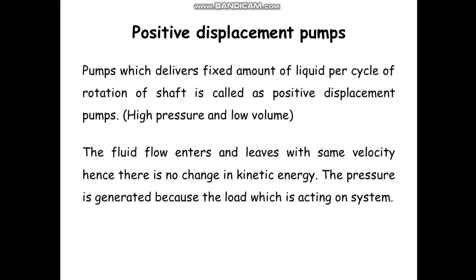So positive displacement pumps, as I already said, deliver a fixed amount of liquid per cycle of rotation of the shaft, and that is why they are called positive displacement pumps. They are usually high pressure and low volume pumps used for hydraulic systems to sustain against some load which creates the pressure inside the system. So a pump never creates the pressure, it creates only the flow. Restriction to flow creates the pressure.